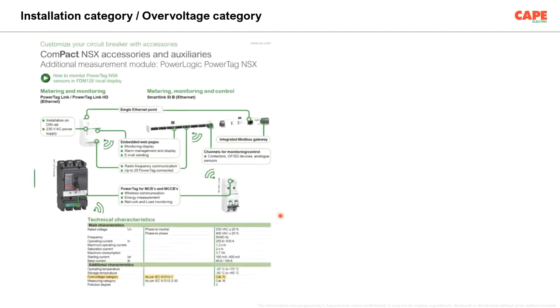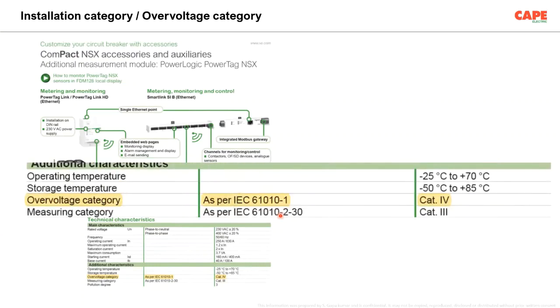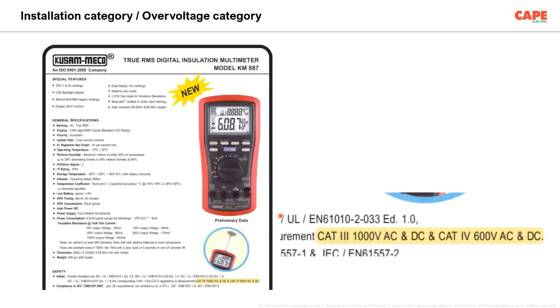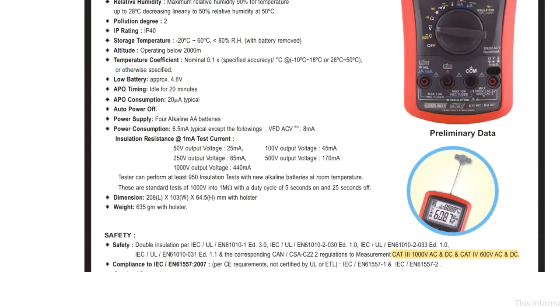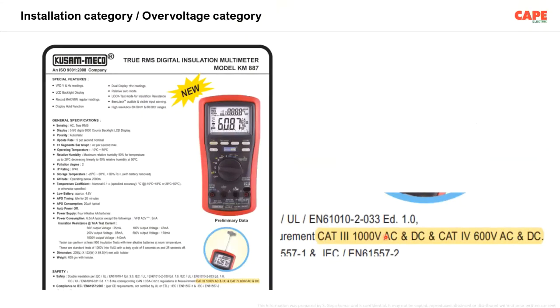How can you see this parameter in the manufacturer's catalog? You can see I'm showing an MCCB catalog, overvoltage category according to IEC 61010-1, category 4. This is a multimeter. You can see here a multimeter with a safety marking. Please note that it is written on the safety part: double insulation, category 3 1000 volt AC DC, category 4 600 volt AC DC.